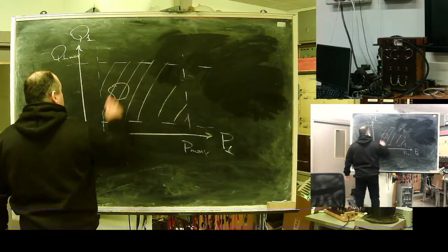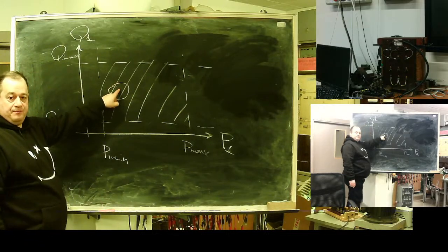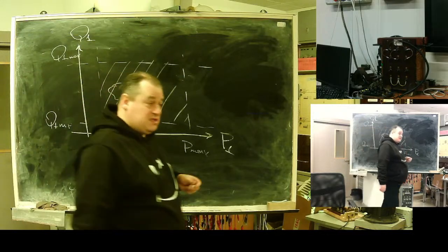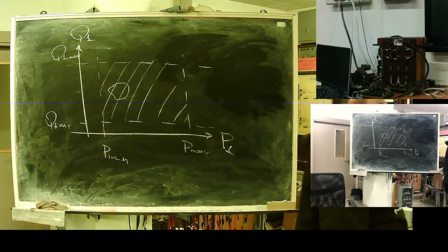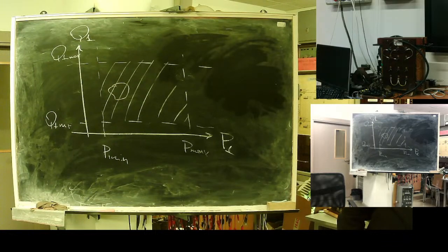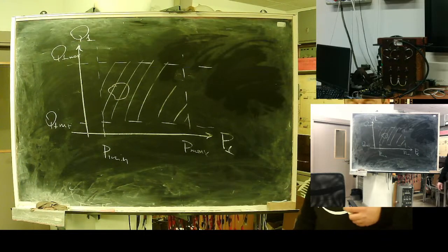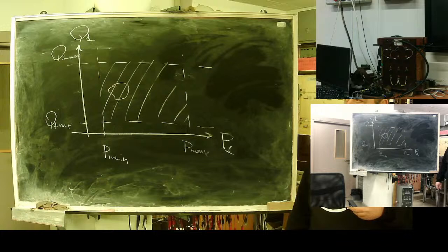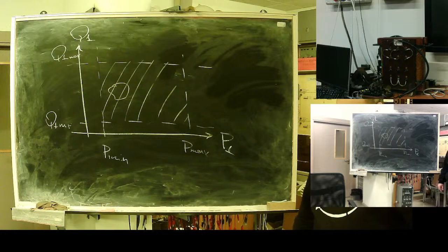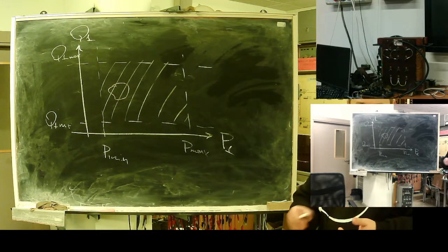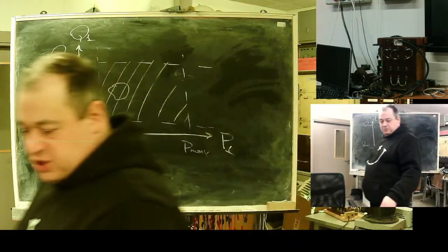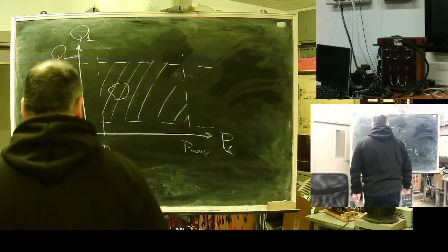With hydropower plants, usually there are areas where you can use this area, but only for 15 minutes, because it's an area of dangerous vibrations. Cavitation problem, vibration problem, or possible overheating problem.